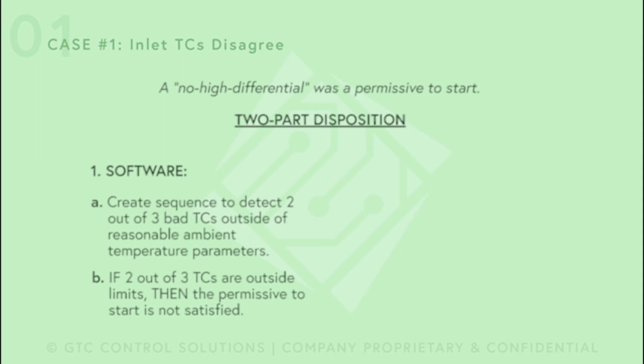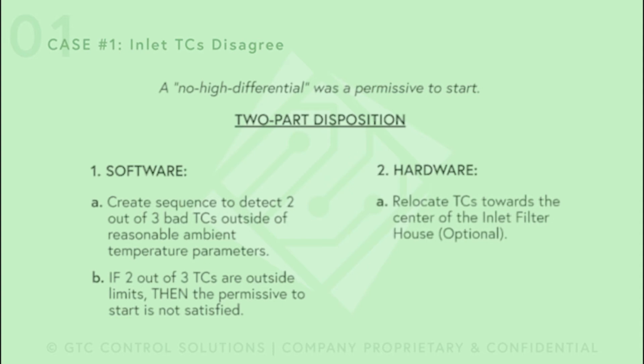Since then they have had very successful starts all the time. At least the thermocouple problem is gone, and that was a single point of failure condition, because with one hot thermocouple, or one too close to the wall, they could not start the unit. The second part of the disposition was that we recommended relocating the thermocouples towards the center of the inlet filter house, putting them 2 or 3 feet away from the center thermocouple to each side, because that's basically what you want: an average ambient temperature in the filter house without actually reading the temperature of the wall. This is how we solved this case. The customer never had another complaint about this issue.